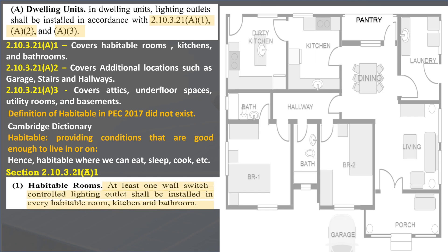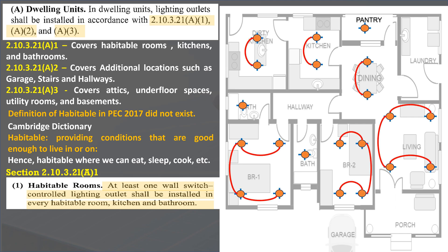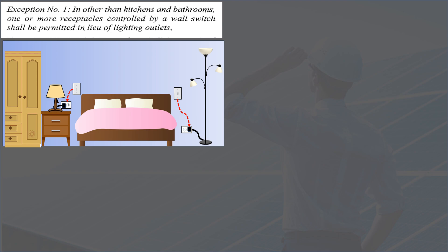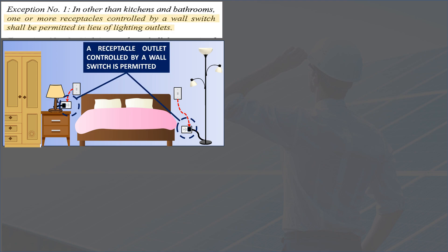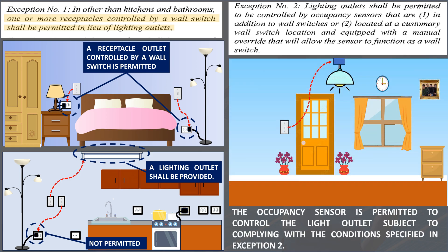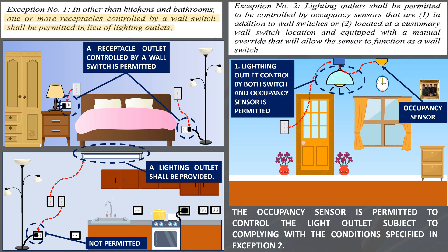Subsection 2.10.3.21(a)(1) states that at least one wall switch-controlled lighting outlet shall be installed in every habitable room, kitchen, and bathroom. The light switch's location is not addressed in the code — it can be anywhere inside the room, but the best place is near the entrance. In Exception 1, a receptacle outlet controlled by a wall switch is permitted to serve as the required lighting outlet in habitable rooms, except in kitchens and bathrooms. In Exception 2, occupancy sensors are permitted for switching lighting outlets in habitable rooms, kitchens, and bathrooms.